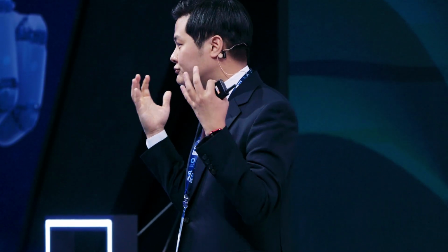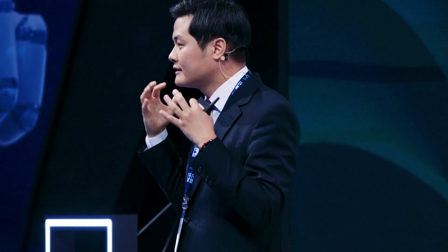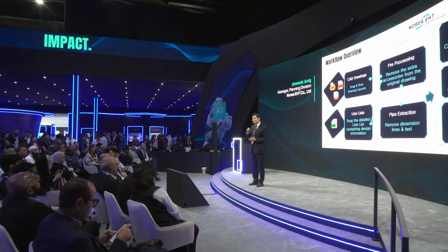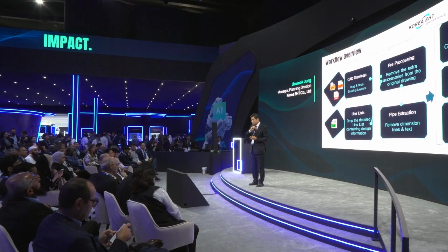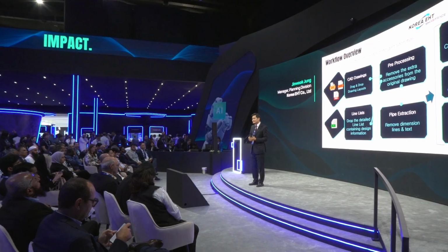And then reasoning LLM, you can think of as a hand. With the rules that it learned from the mechanical drawing, and with the rules which it already has regarding the heat trace drawing, it draws the heating cable on the isometric drawing in an optimized way.